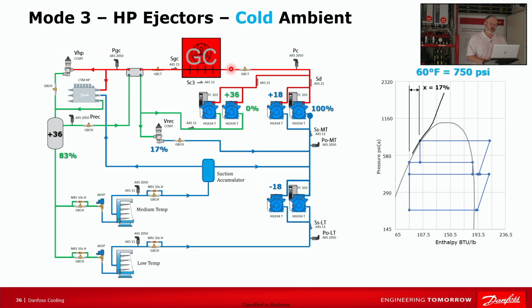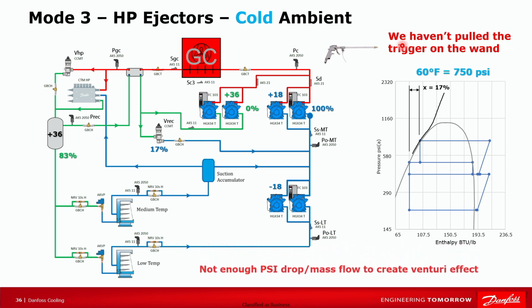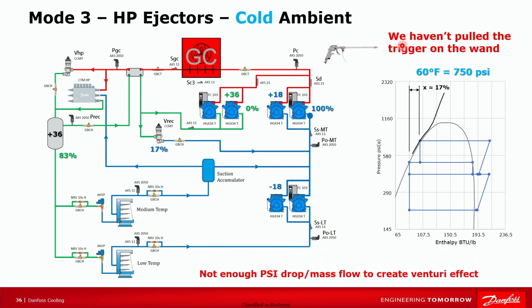So here we'll notice nothing went to parallel compressors. And the reason is we haven't pulled the wand, the trigger on the pressure washer wand. Back to that example, there's not enough pressure drop across the ejector block. And there's not enough mass flow because it's a cooler ambient. We're not running everything. We can't create the Venturi effect. And this is a new line here. This is our suction accumulator. We piped from here over to the inlet of the ejector block.